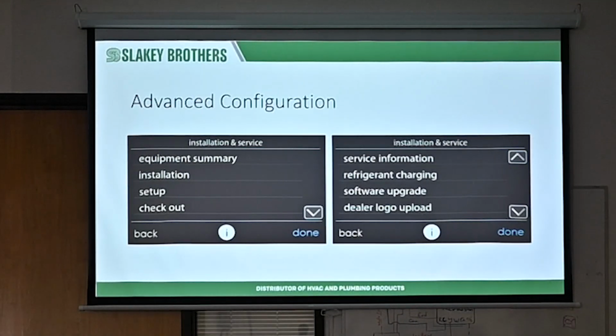So this is where you pretty much do a lot of stuff. Like if you need to look for software upgrades, if you need to update the software on it, or if you want to find out if there's a software update available for it, you go there. Now, refrigerant charging is white right now, because when they were helping us out to get us these slides, this unit was connected to a variable speed unit. Refrigerant charging is only available on the variable speed stuff. And what's really, really cool when you get to the Evolution Extreme stuff is that it's registering pressures, temperatures, subcool, superheat, it does it all for us. Really, really nice.